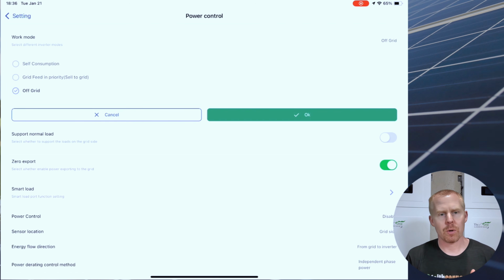The off grid work mode ends up kind of changing the way that the AC input works on the inverter. Anytime power is detected on that AC input, the inverter is going to switch over to that AC input connection. It's kind of like the way Victron works for like the RV aspect. So you're running off batteries and then you plug into shore power and you want to power all your loads from shore power as soon as that shore power is connected. That's kind of like what off-grid mode does on the MidNite inverters.